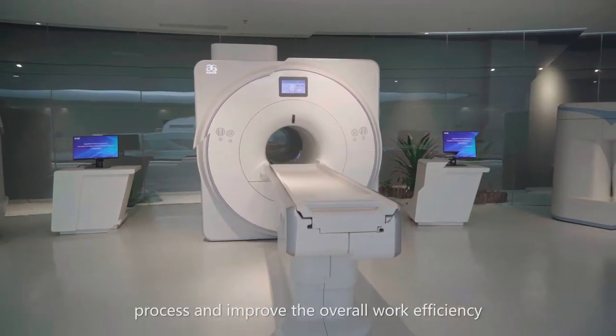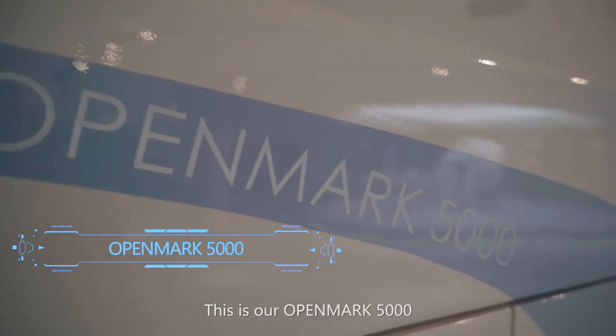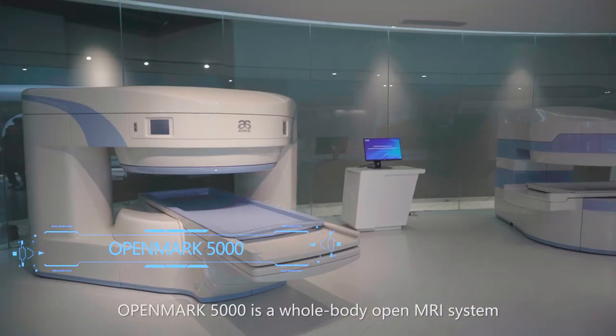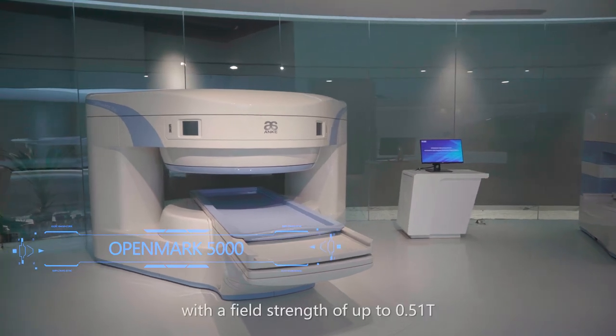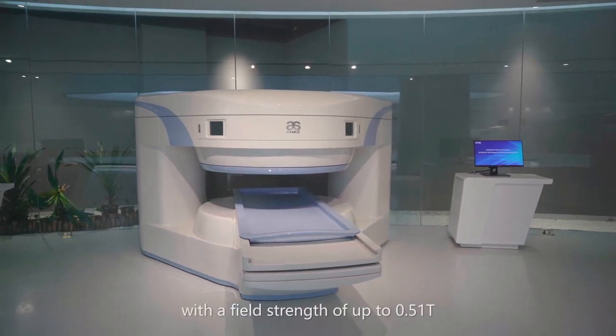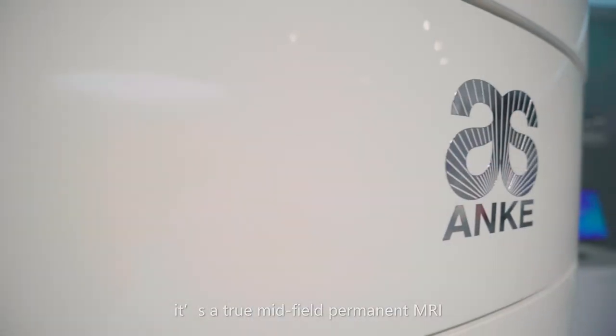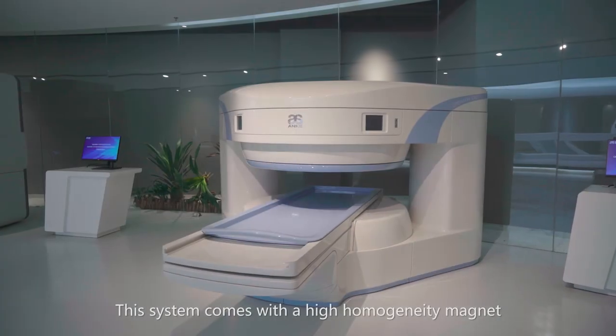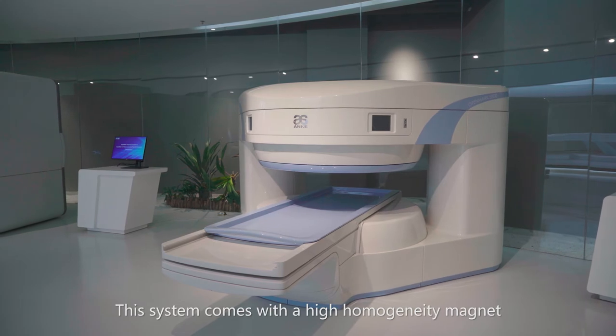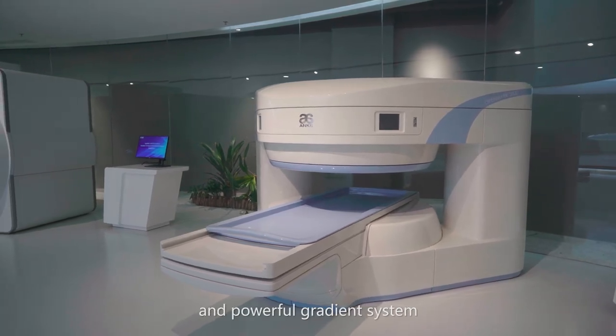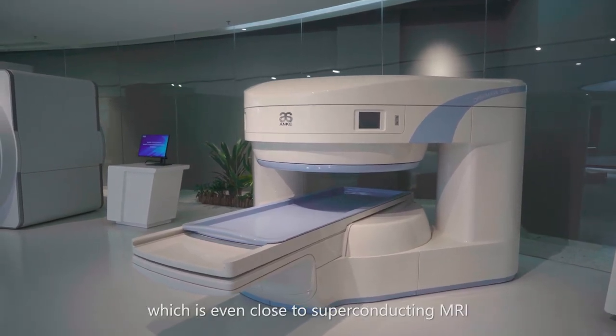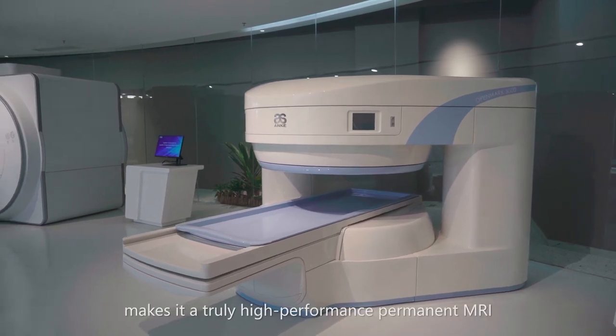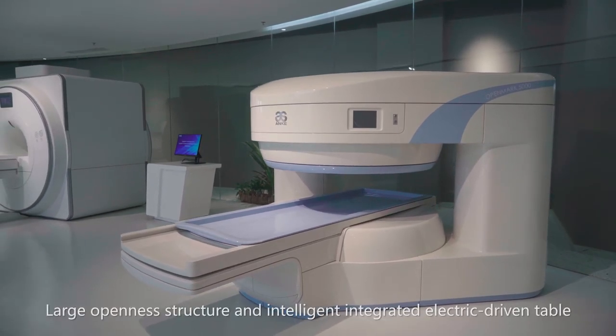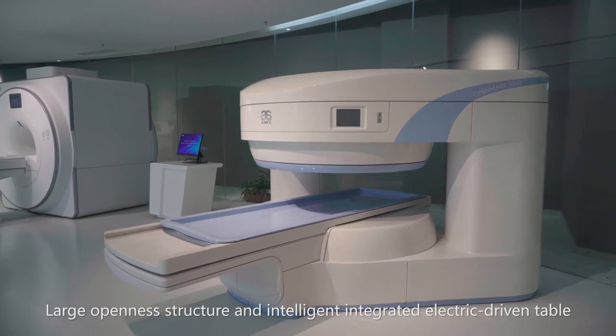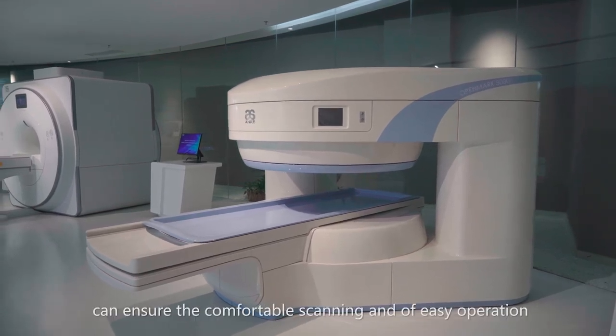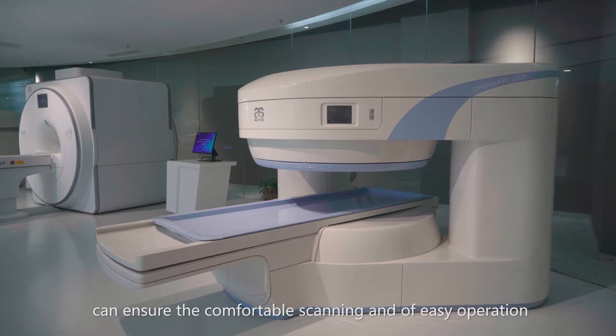This is our OpenMark 5000. OpenMark 5000 is a whole body open MR system with a field strength of up to 0.51 Tesla. It's a two-pole permanent MRI. This system comes with a high-homogeneity magnet and a powerful gradient system, which is even close to superconducting MRI, making it a truly high-performance permanent MRI. Large openness structure and an intelligent integrated electric-driven table ensure comfortable scanning and easy operation.